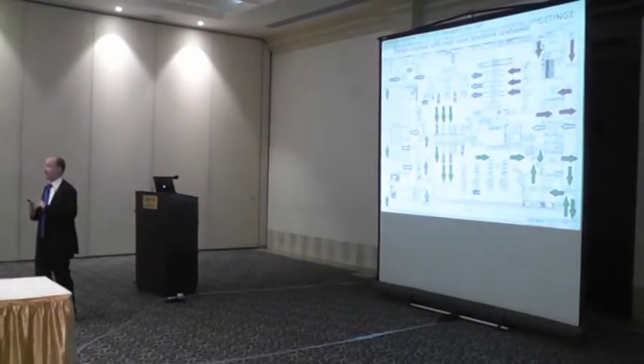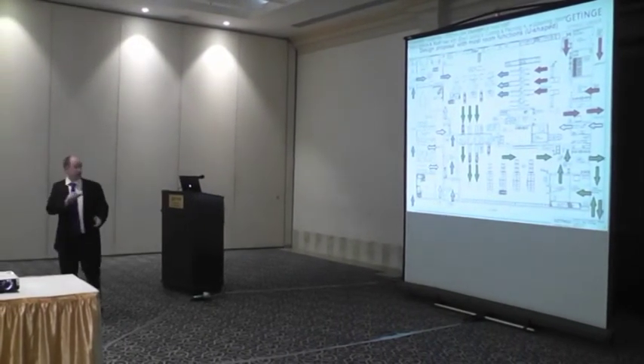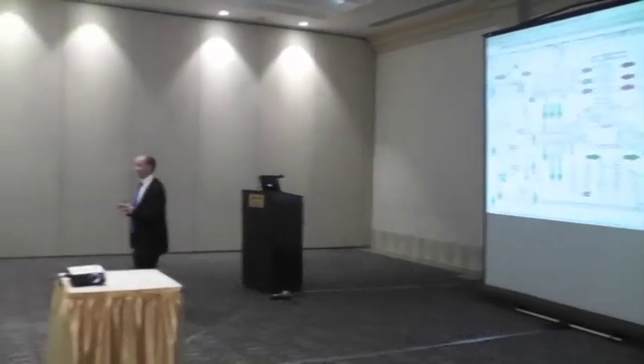Now we have 3 different techniques for heat sensitive items. We use low temperature steam with formaldehyde. You have the ETO technique that requires a separate room. And we have the plasma technique that is also in this area. But for linen and the instruments, that is exactly the same sterilizer. So there is no need for different ones in that aspect.